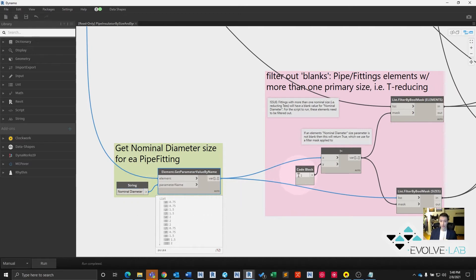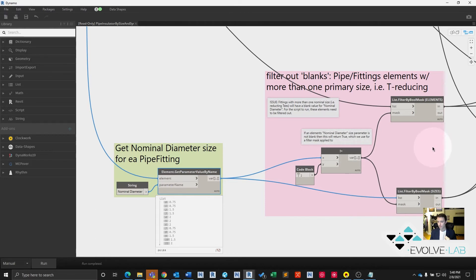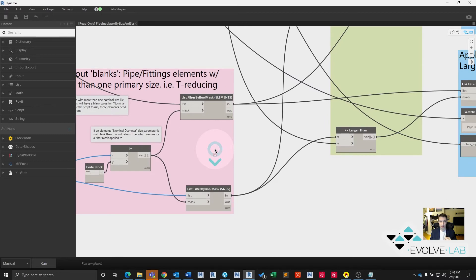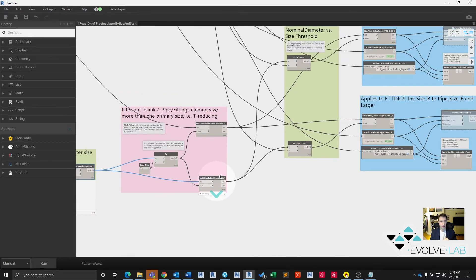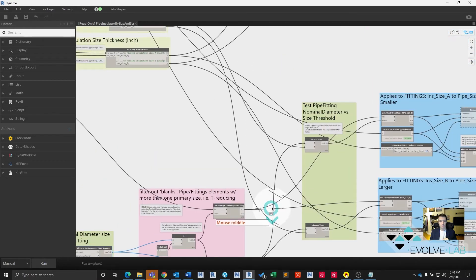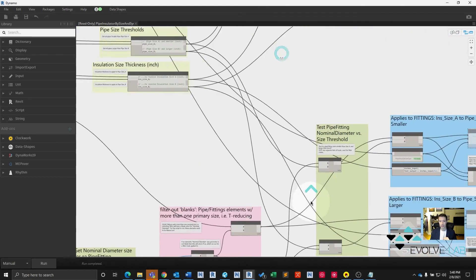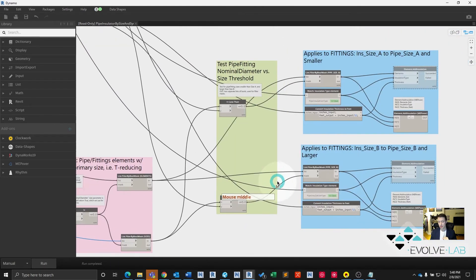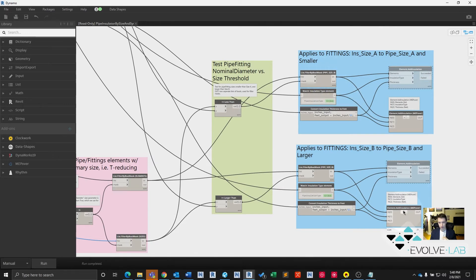This will happen and it'll return a blank size if it's a fitting that has more than one opening size to it. So we're going to filter these out so we don't get any null values from this part of the script. And then using that filtered list of fitting elements and sizes, we're going to do the exact same process here that we did up here. Get the size, check it against size A less than or size B larger than, and then convert to feet, grab the insulation type, grab all the fitting elements that we're supposed to grab for that size and apply the insulation.